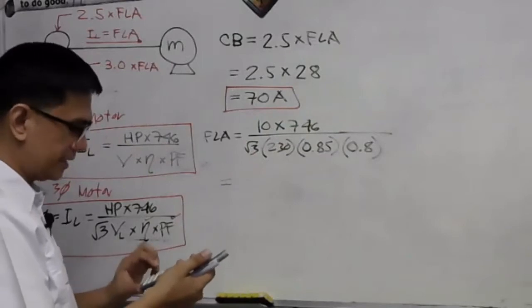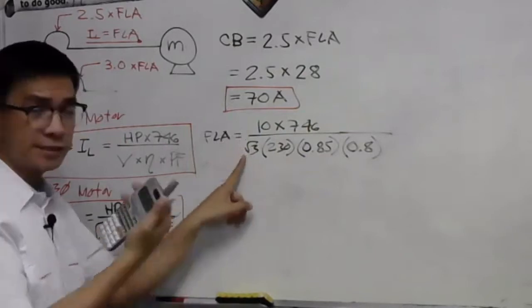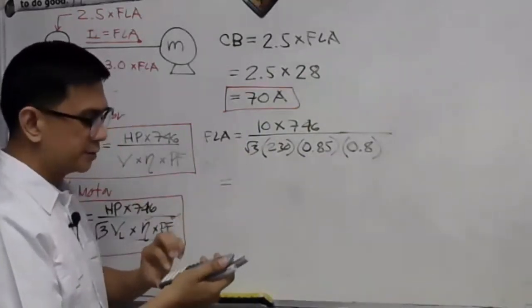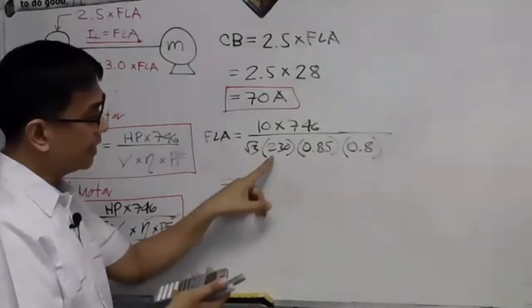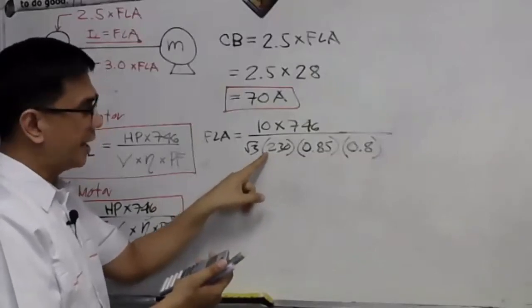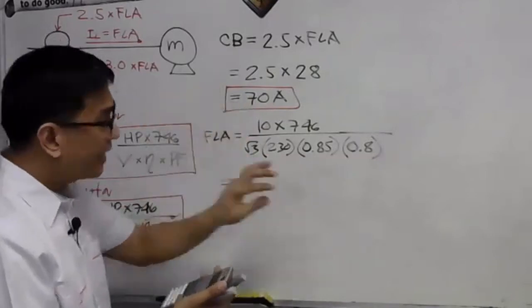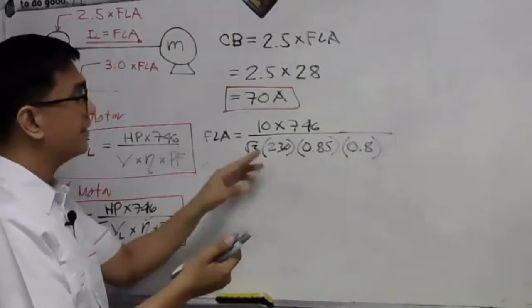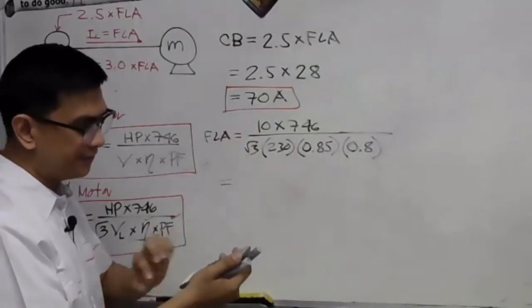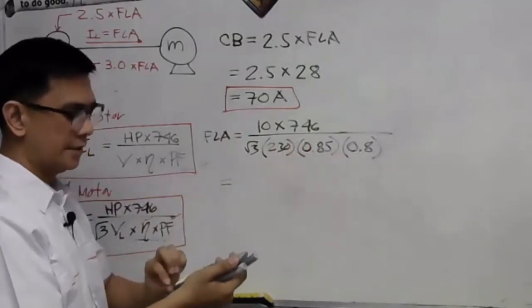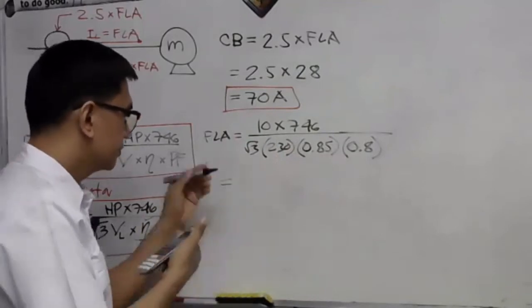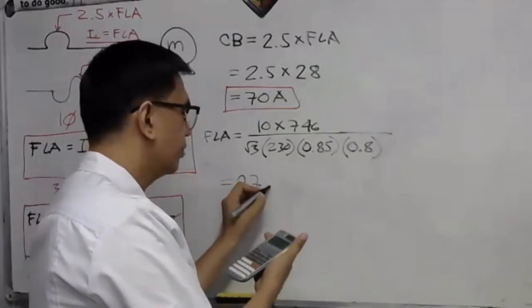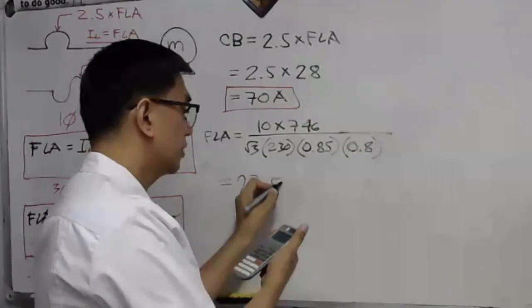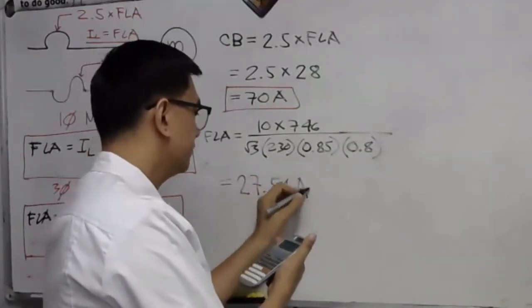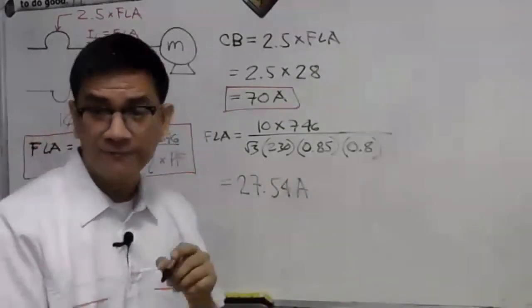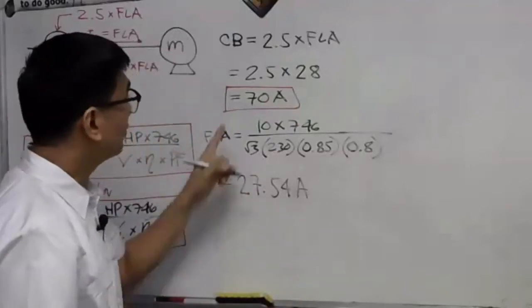We have 10 times 746. Then in your calculator, you press divided by square root of 3. For me, it is easier. After dividing by square root of 3, you press divided by 230, then another divided by 0.85, and then again divided by 0.8. And our answer is 27.53857, which is quite near to your 28 ampere here, right?